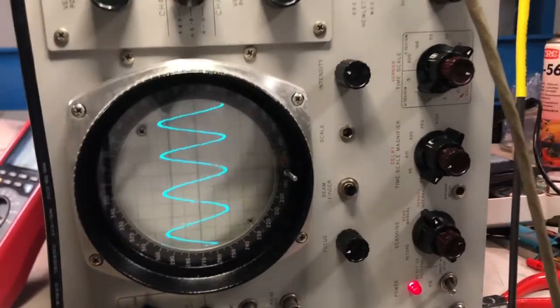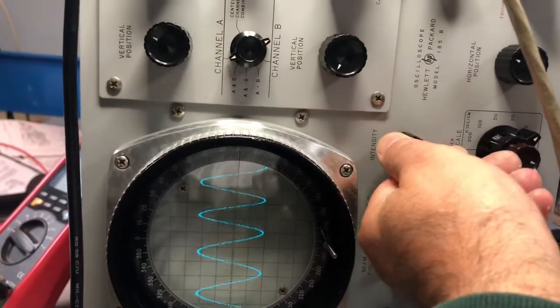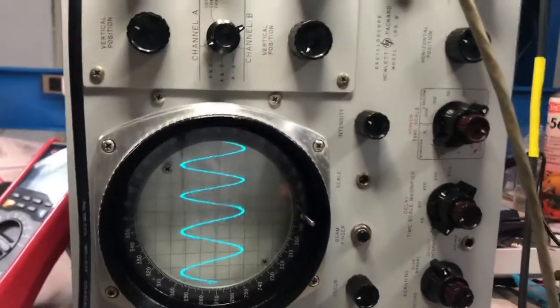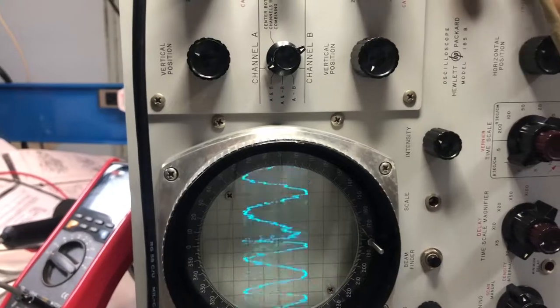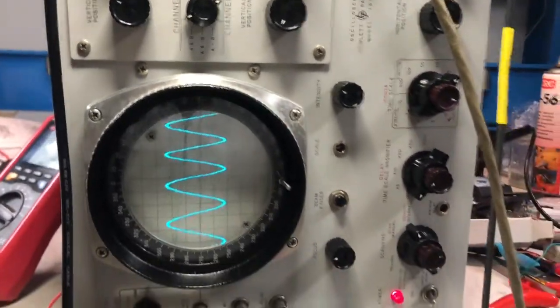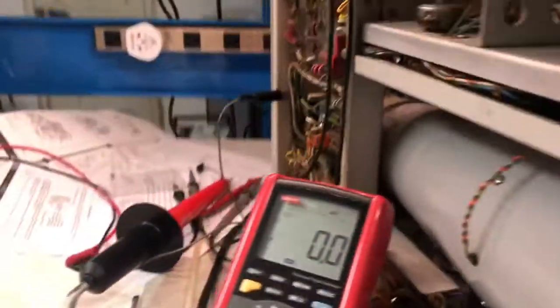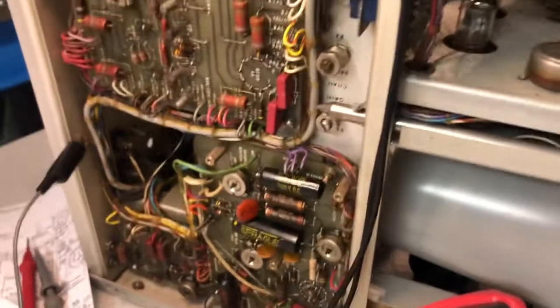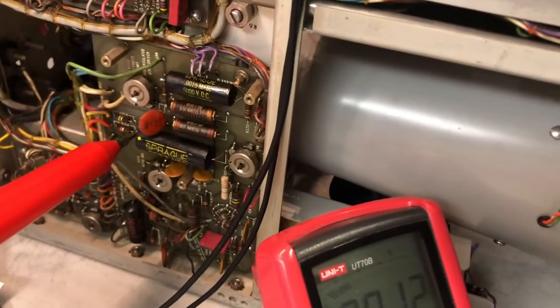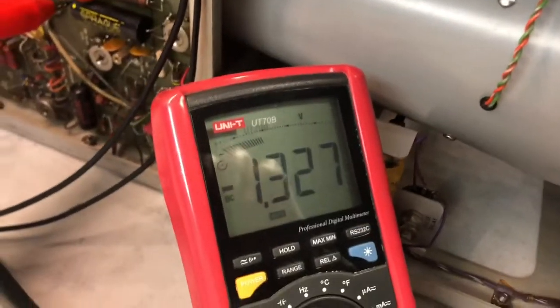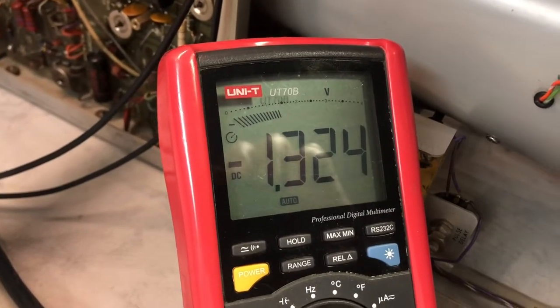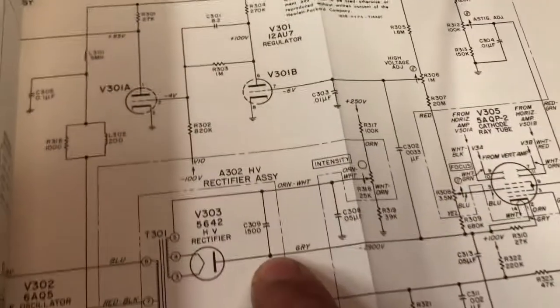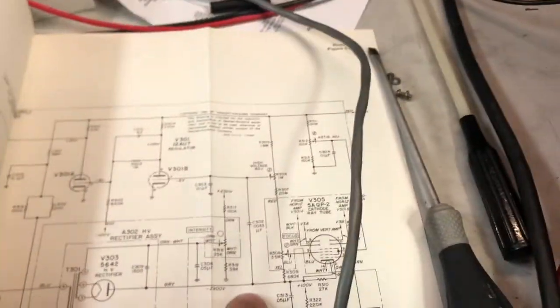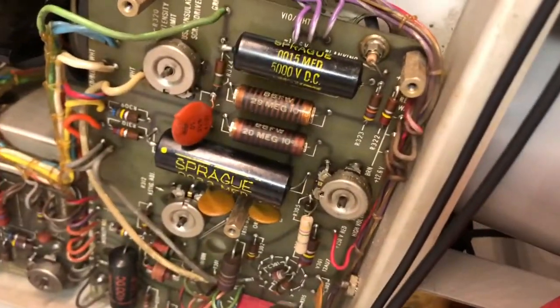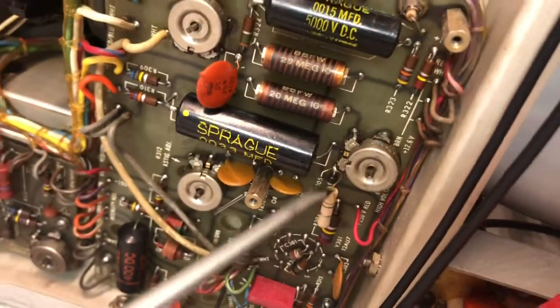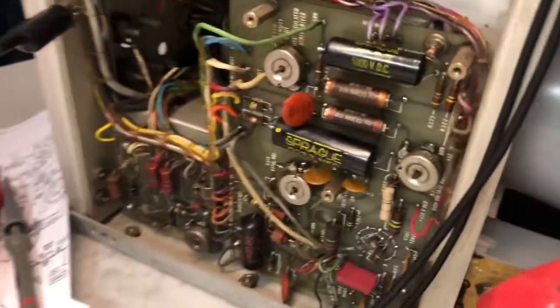Well, you know, by the fact that the intensity is pretty high, I would never have suspected that I could have a problem with the high voltage, but indeed I have it. And look at that, I'm going to probe it. Here I should read minus 2900 and I'm at minus 1300. So I suspect that we have an issue, and there was an issue, since here there is a resistor mounted on another one. So for sure we have some problem.